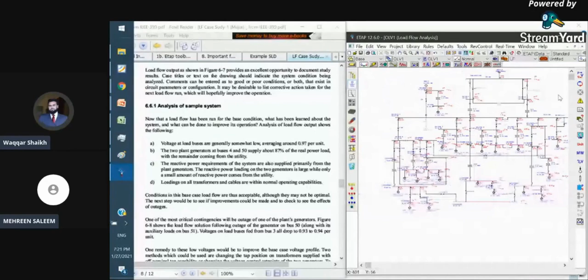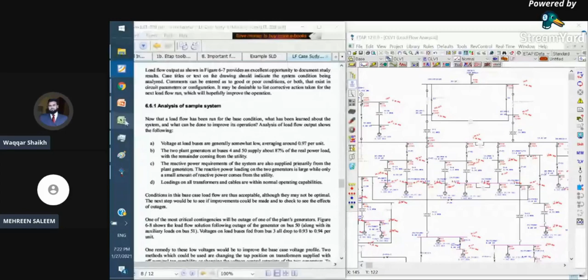The third thing is that the reactive power requirements of the system are also supplied. Now the second point was about the active power. Okay, the third point is about the reactive power. The reactive power is primarily coming from the plant generation. If you see here, the two generators are supplying more reactive power, whereas the reactive power coming from the utility is 196 kVAR only. So this is the third verification in this study. And the fourth verification is that loading on all the transformers and the cables is within the operating range.